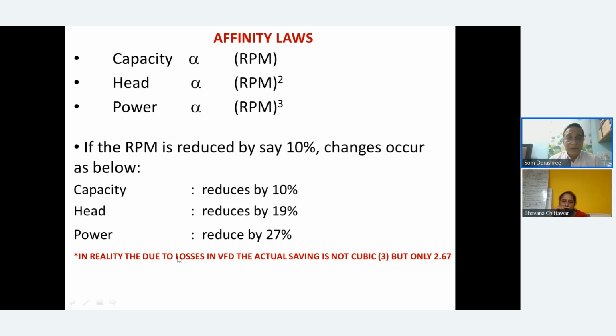In reality, due to losses in the VFD, the actual savings are not cubic. Practically we have seen, and it has been demonstrated in many places, that you will not get the cubic saving, especially when you do energy audits, etc. You should take a very conservative saving of about 2.67.